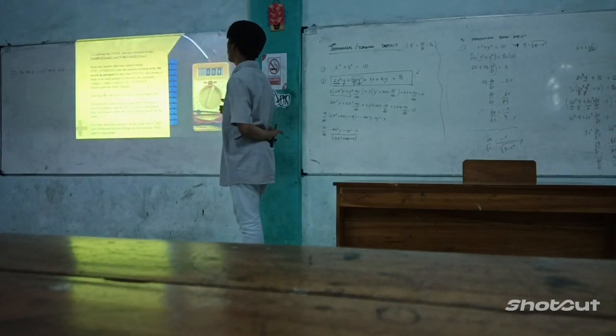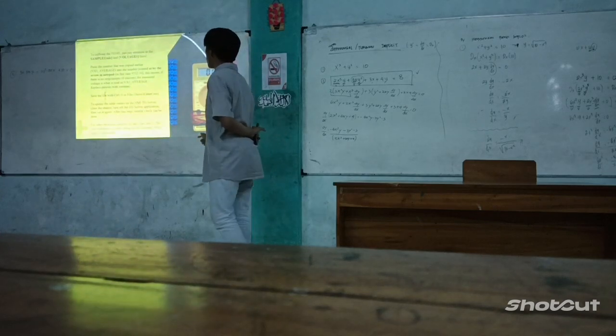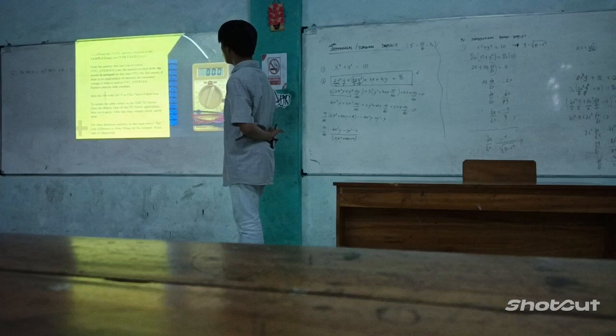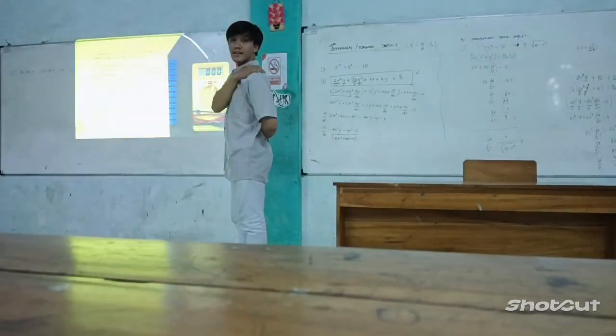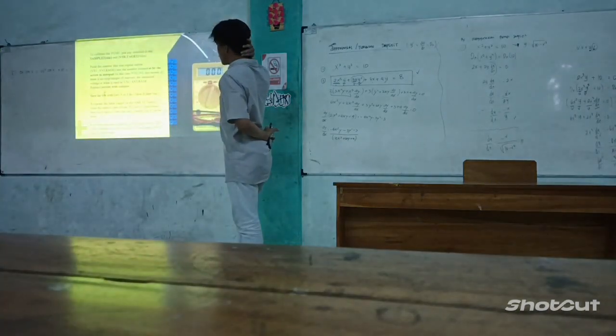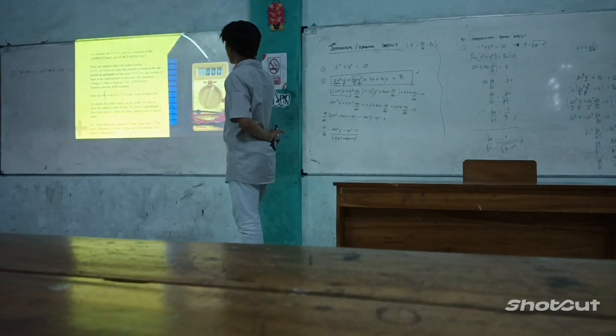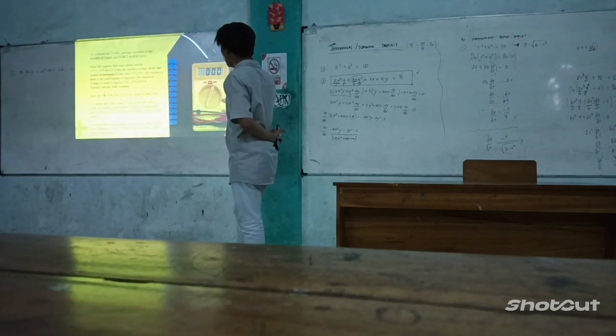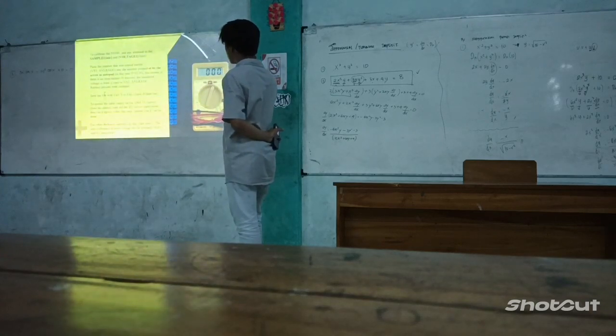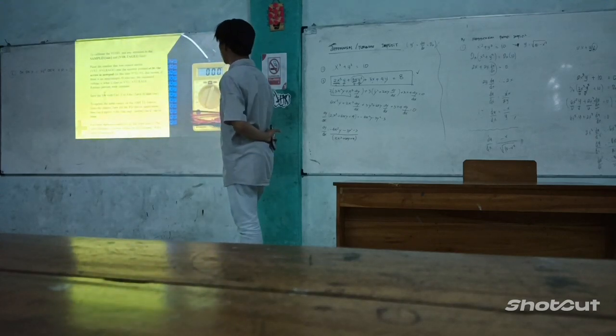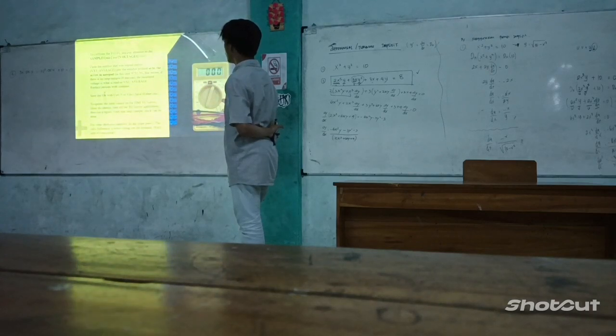To calibrate the TG 101, just pay attention to the sample 1 background and the voltage 1 lines. Paste the number that was copied earlier, the PX1 average, into the number pointed at by the arrow in notepad. In this case, 97052.56. This means that if there is no slip at the sample 0 micron, the measurement voltage is read in the PX1 average.